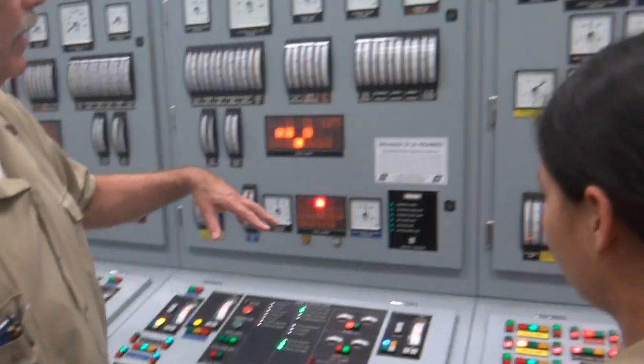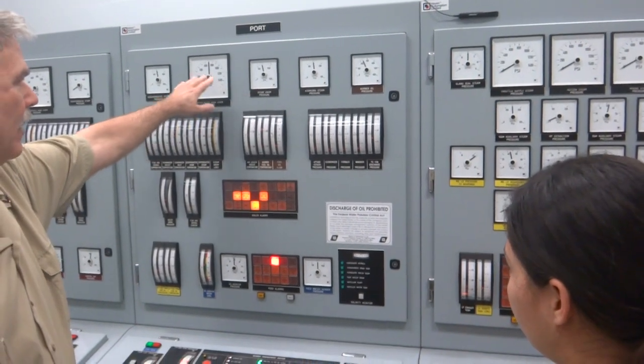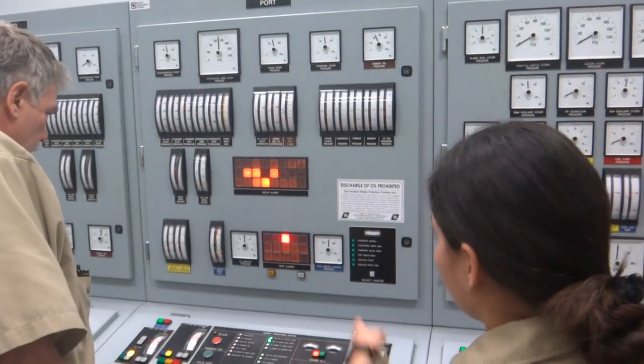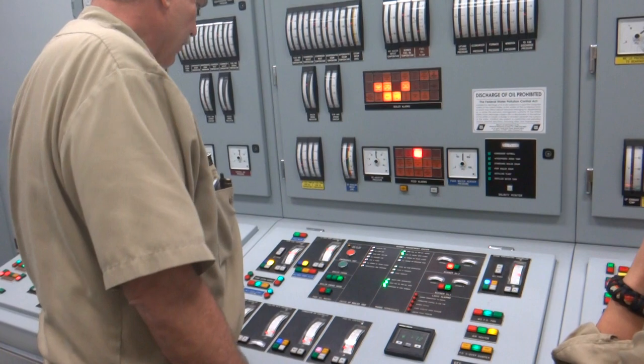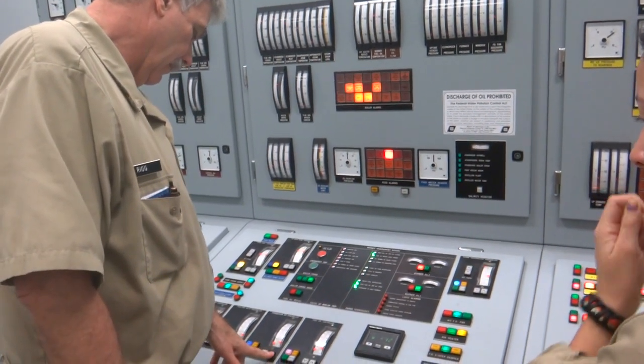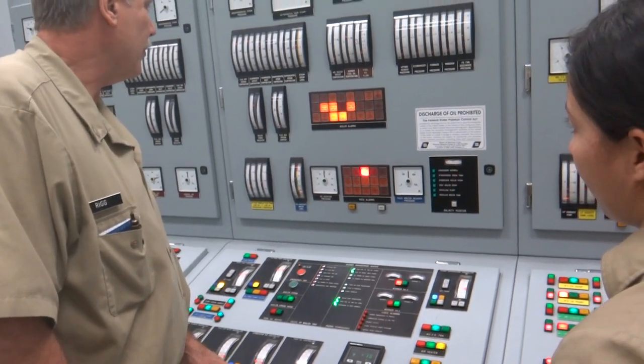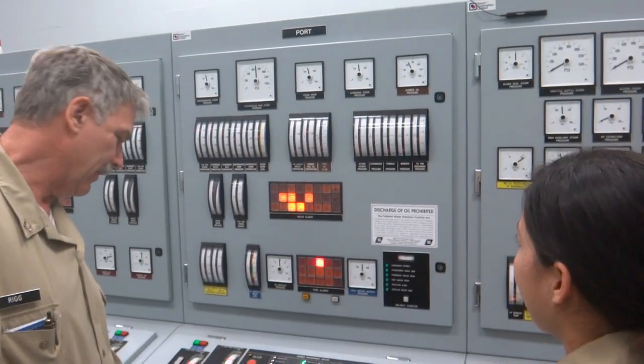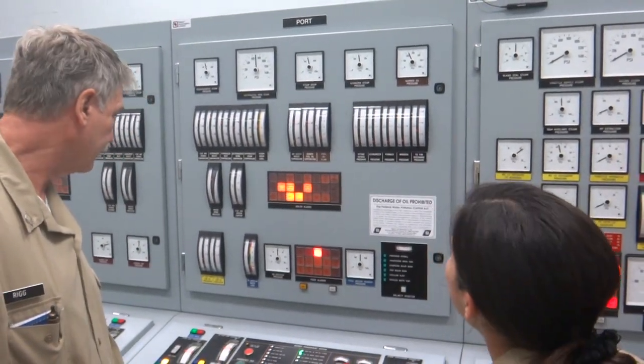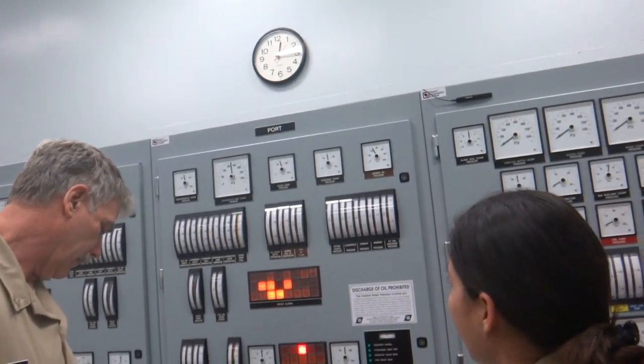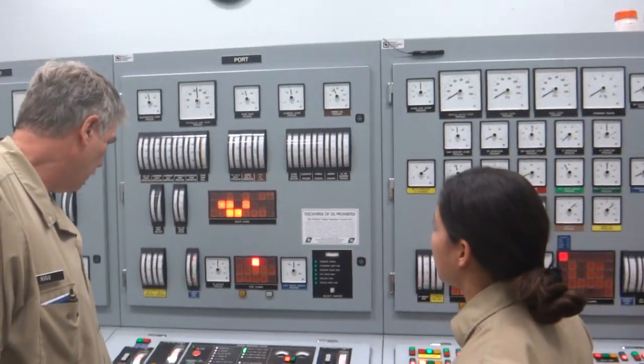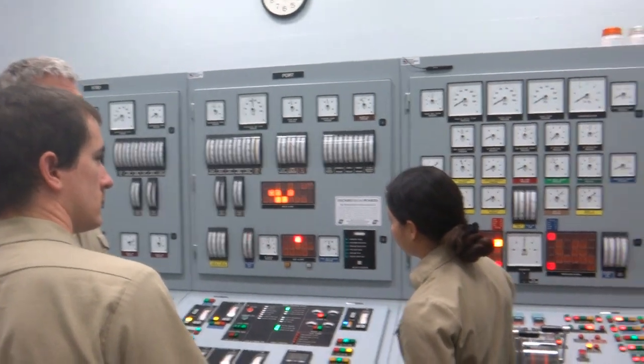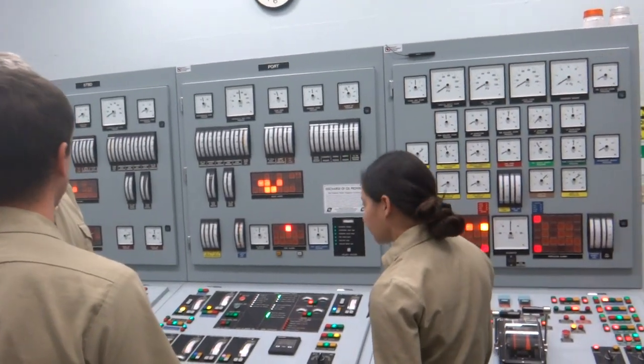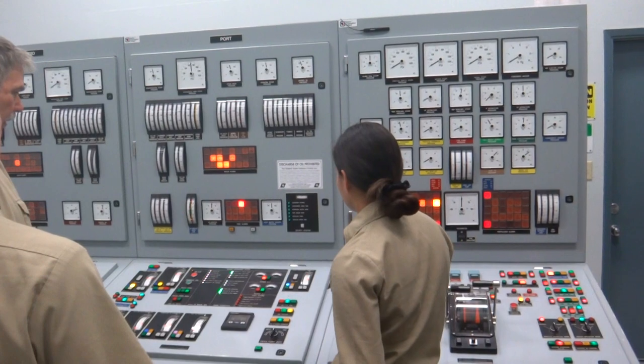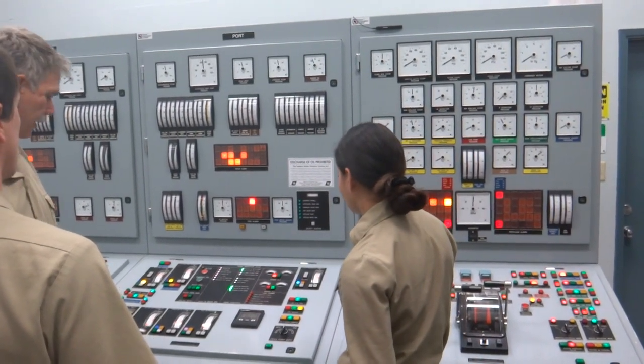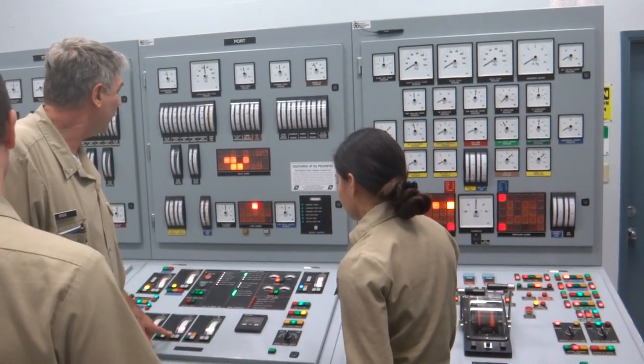Okay, I cut out one burner, adjusted the oil pressure. We're smoking white, nope, smoking black. Because we were, look at the pressure, it's up to 700. We have to stay within that 3.5-hour limit, right? So when you're firing up the plant, like in a real life scenario, does someone stand here and monitor it and slowly bring up the pressure? You can have the first, the second, watch stander down there probably. Okay, so that will control the firing rate.